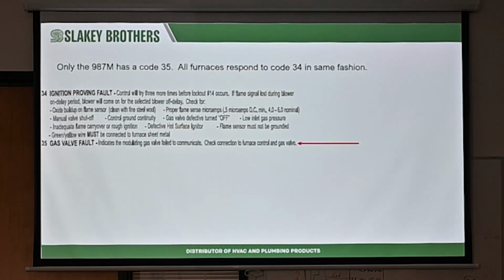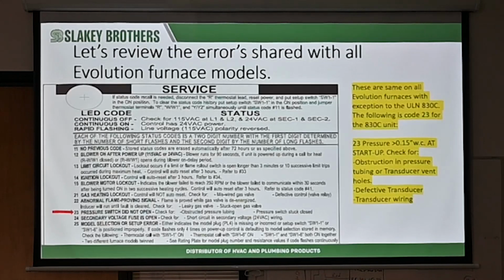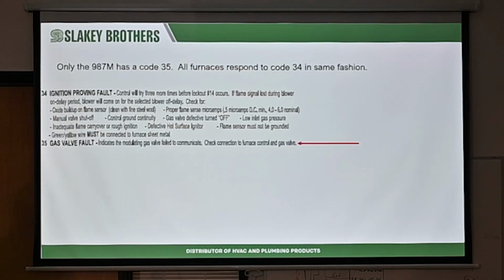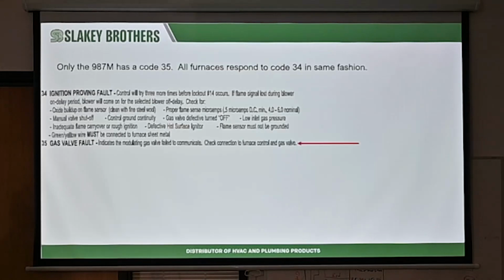I think it's the next page. Yeah, these are going to go hand in hand in regards to the ignition proving. So 34, ignition proving fault. They all have the same thing. The most common thing is just it's not sensing the flame, either because dirty flame sensor, bad board, or the gas valve isn't even opening up. There's no flame at all.